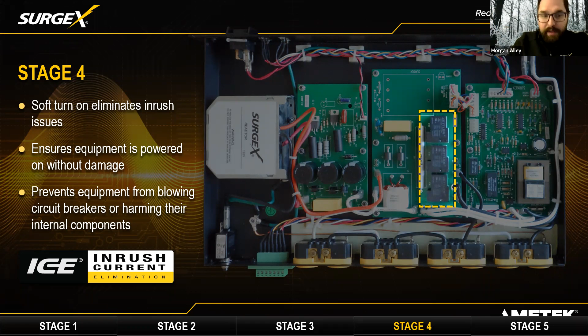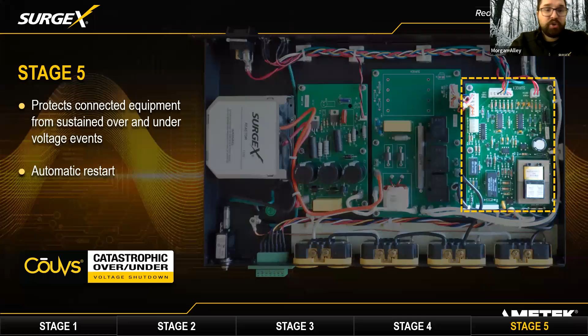And then we have COUVs, for catastrophic over or under voltage. I showed you over voltage, where the sine function's peaks and valleys are really high, and under voltage is the exact opposite. COUVs detects over and under voltage situations and will automatically restart in case of that situation. They're generally not as dramatic as a massive surge in terms of degradation of equipment, but over and under voltage can instantaneously destroy equipment, though most of the time it will just degrade the lifespan of the product we're protecting. So we use all of these different approaches when it comes to eliminating surges and filtering power from noise, inrush, and over-under voltage.